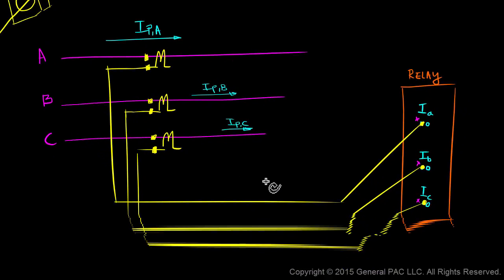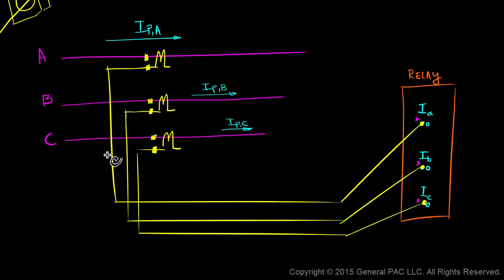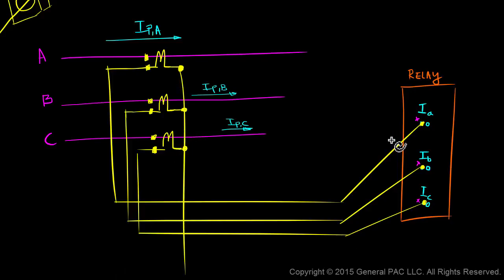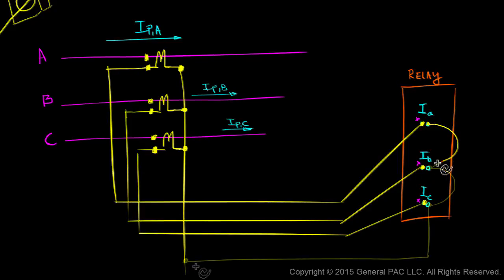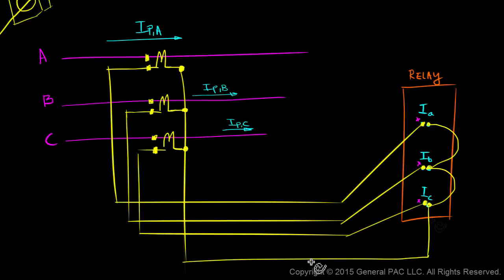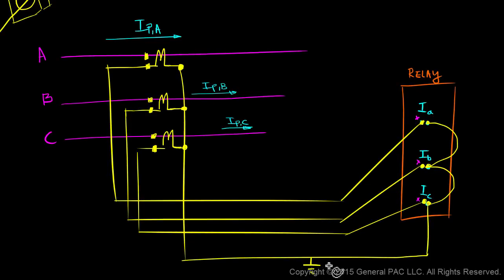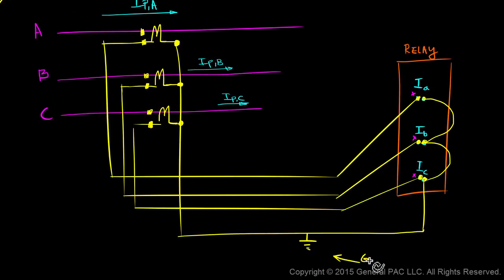Since our goal is to connect these three CTs in Y, we have to take the non-polarity side of phase A, phase B, and phase C CTs and connect them together. The non-polarity side of the input terminals of our relay must also be connected together, and one of these points must be grounded. We'll talk about this ground point more in-depth in a different module.